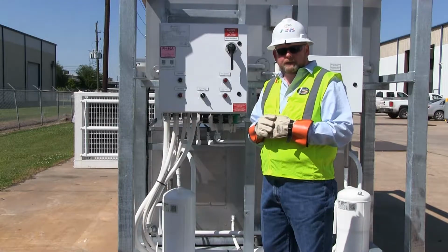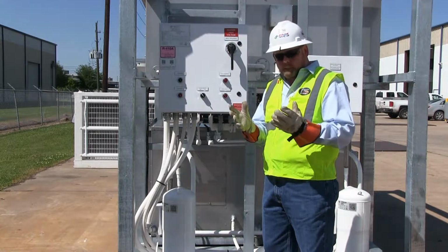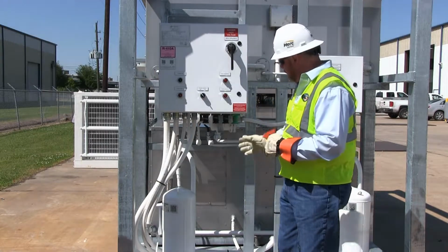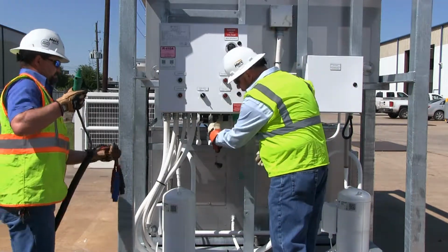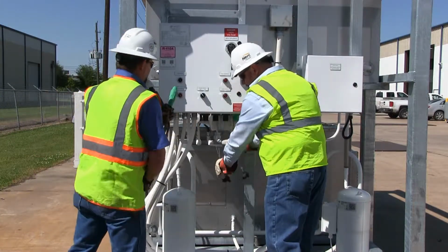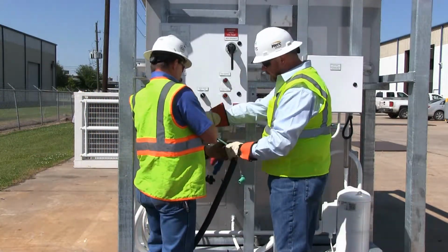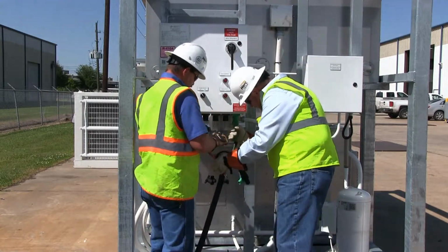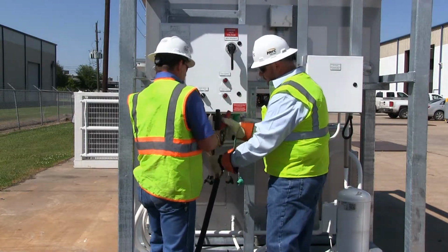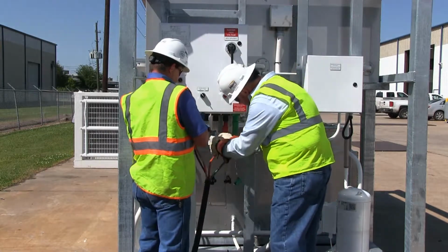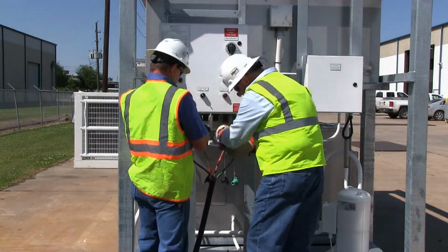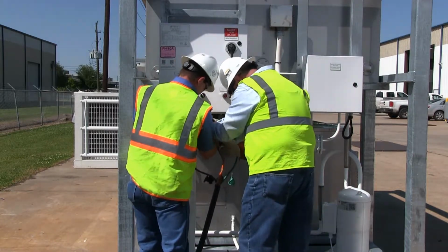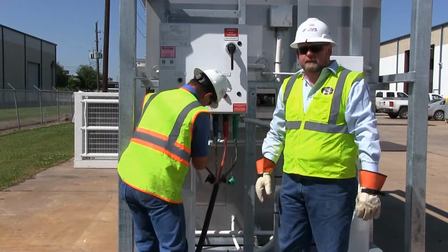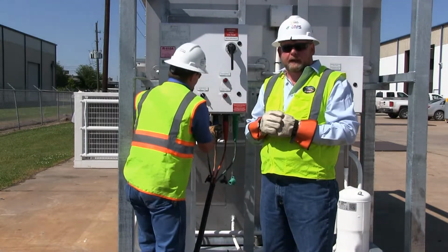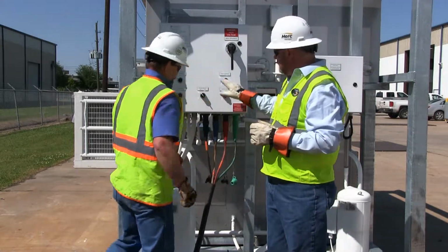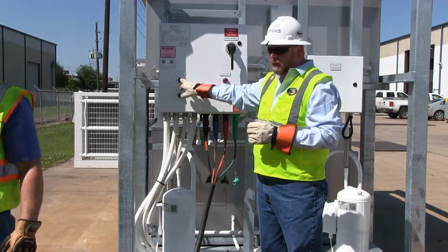We verified the machine is going to require 100 amp service, so with the proper PPE equipment, we're now going to hook up the cam locks. To remove the protective caps for each one of the legs, we're going to tie in the cam locks. You always tie in the ground first, and then follow your color sequence for the phasing. Once the cam locks are hooked up, we're going to energize the machine and check for rotation, and that will be indicated by the phase incorrect and the power light here.